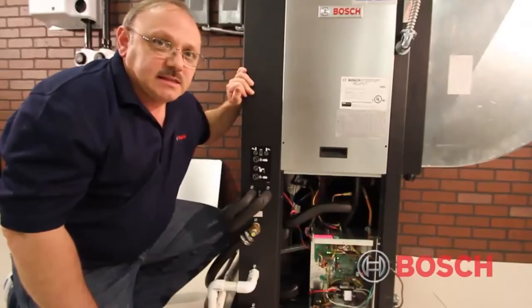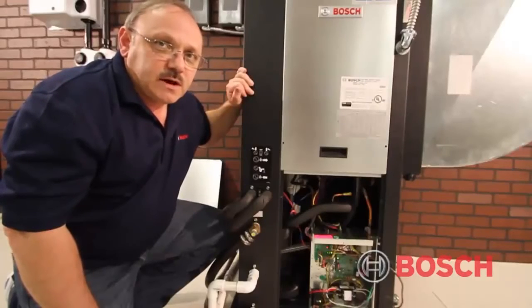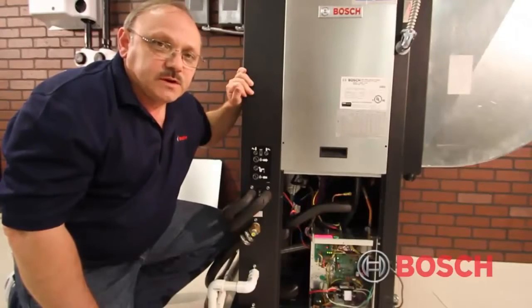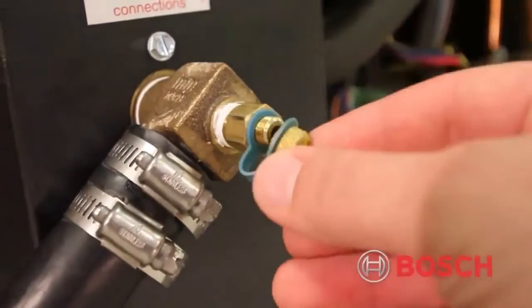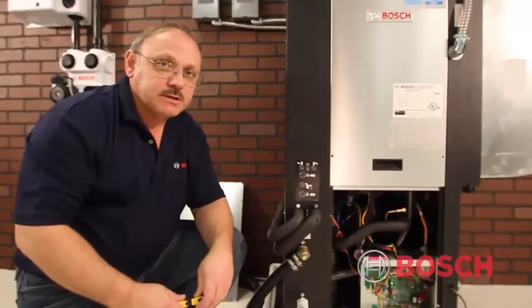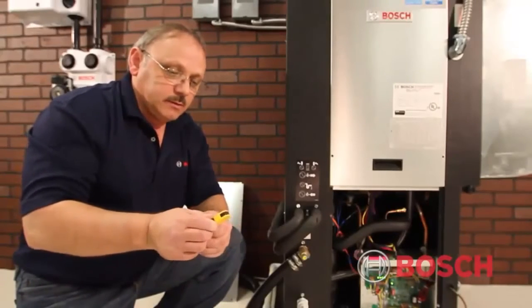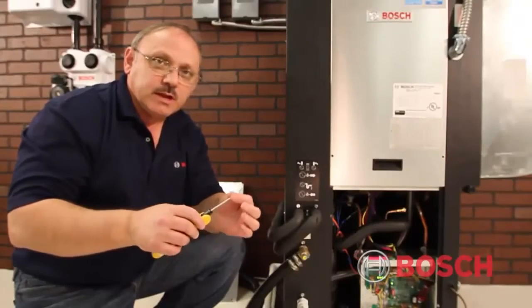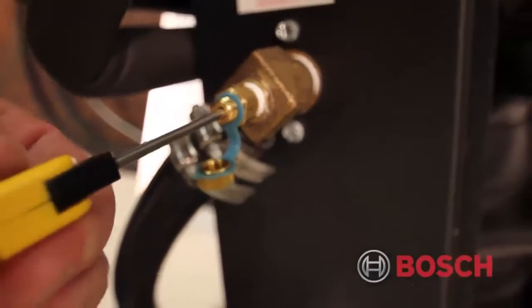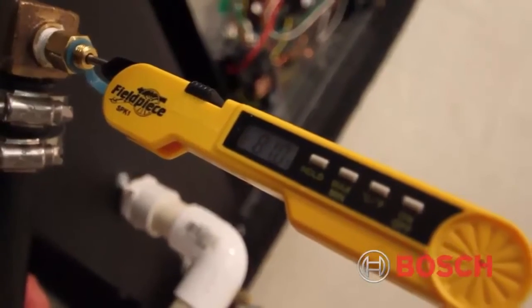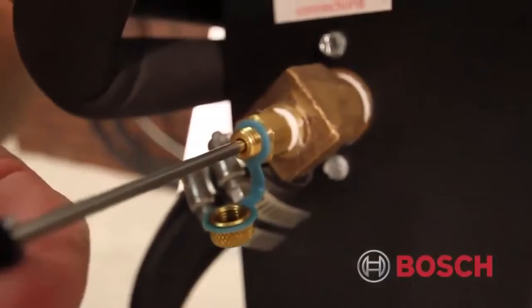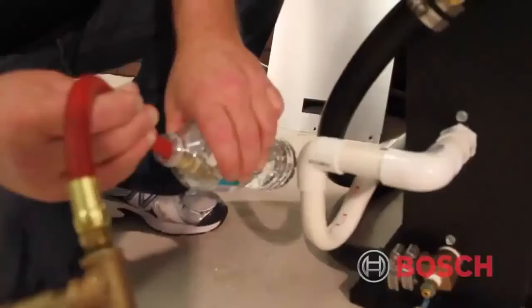Now, just because the lights indicate that is the mode of operation it should be in, we always want to verify that we are in second stage mode of operation by checking the current draw on the compressor. In the second stage mode of operation, the current draw will be approximately 25% higher than it is in the first stage of operation. So once we've verified that we're in second stage of operation, we can continue with our waterside diagnostics. Okay, with the unit operating, the first thing we'll do is remove the caps from the PT plugs, and we'll take an insertion type thermometer and insert it into the PT ports once we've lubricated the stem on the thermometer, and we'll take a temperature measurement of the water entering the coax and the water leaving the coax. Then we'll remove the thermometer, and we'll take our pressure gauge. We'll take the PT port adapter on the pressure gauge, and we'll also lubricate that.